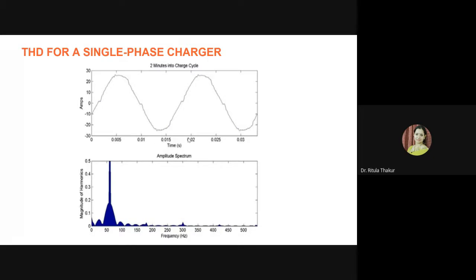Now from these figures, what you can see is that initially, as I said, the effect of the harmonics is not that high. As you can see, the current is almost sinusoidal during the beginning of the charge cycle. Even if we see the magnitude of the harmonics, because it's a 60 hertz system, the fundamental is prominent. The third harmonic occurs around 180 hertz, and the fifth harmonic around 300. They are there, but they are very small as compared to the fundamental.